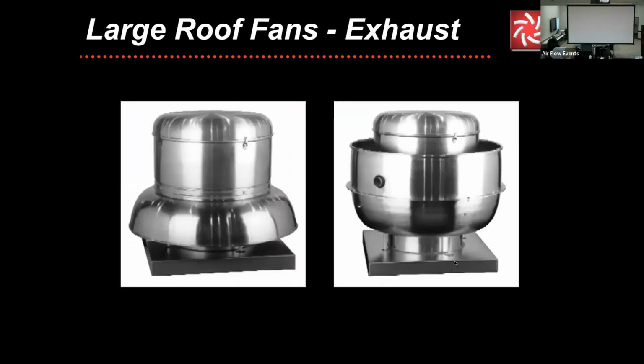Being the spun power roof ventilator, different parts of the country, different folks like to use the downblast. Some folks like to use the upblast. From that standpoint, the upblast style does create fewer turns in the airflow, so it uses less energy. Depending upon your CFM and static, it can use significantly less energy.